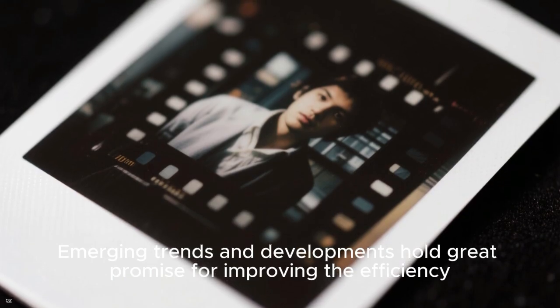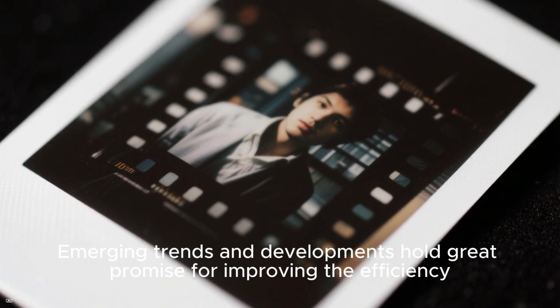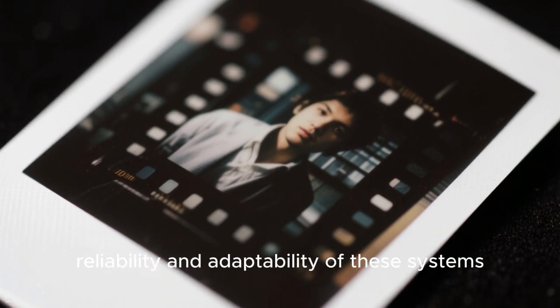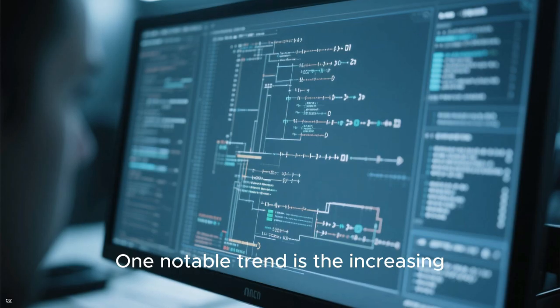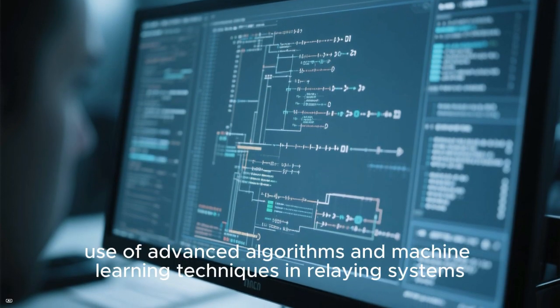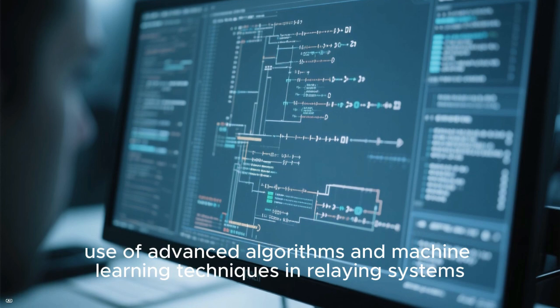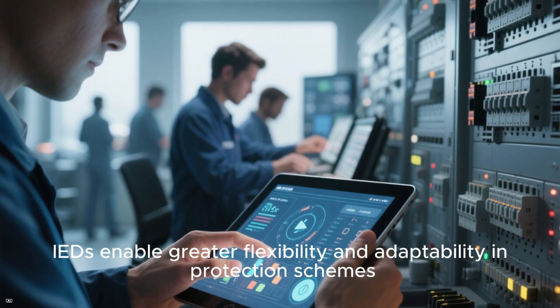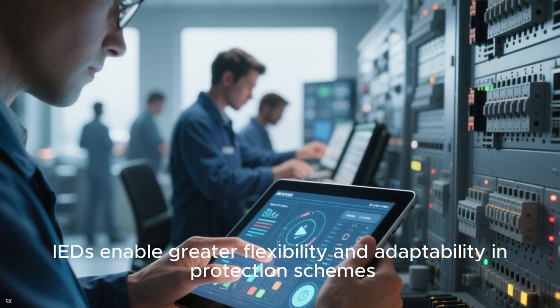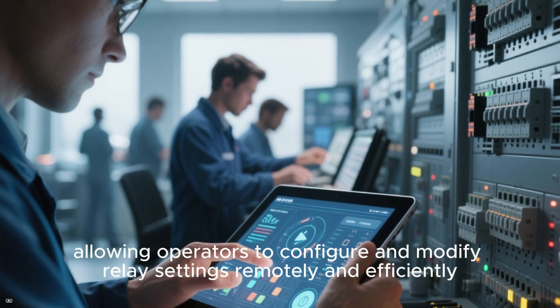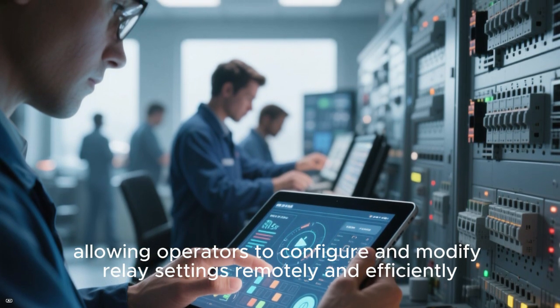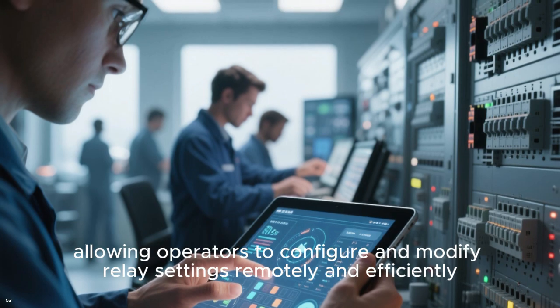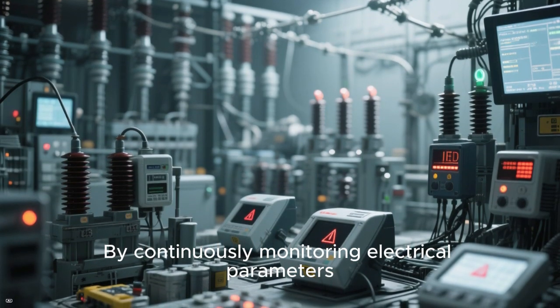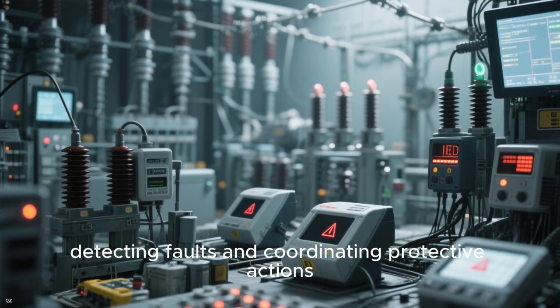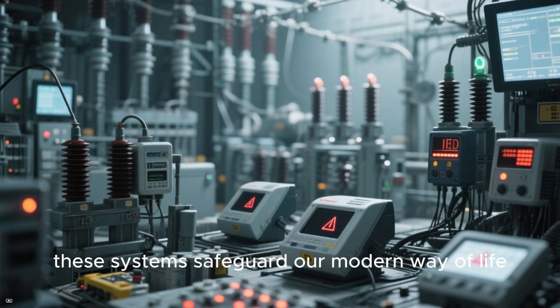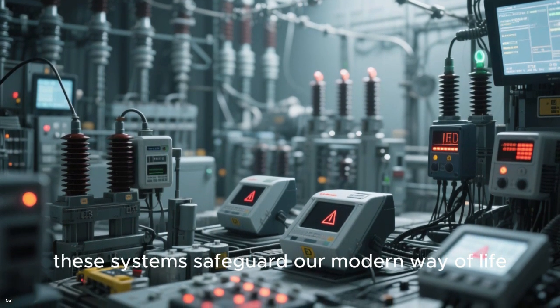Emerging trends and developments hold great promise for improving the efficiency, reliability, and adaptability of these systems. One notable trend is the increasing use of advanced algorithms and machine learning techniques in relaying systems. IEDs enable greater flexibility and adaptability in protection schemes, allowing operators to configure and modify relay settings remotely and efficiently. By continuously monitoring electrical parameters, detecting faults, and coordinating protective actions, these systems safeguard our modern way of life.